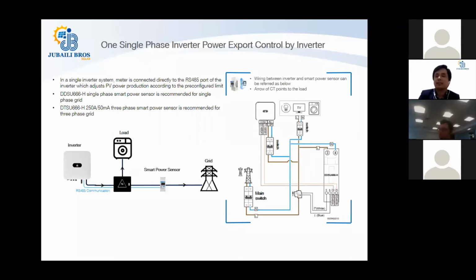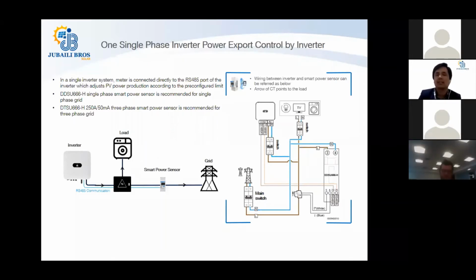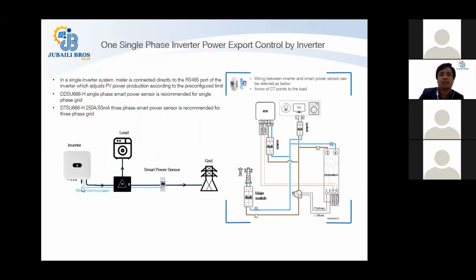This power meter will read the voltage and current, and will understand what exactly power is flowing in which direction. When it goes towards the grid, it will understand that there is excess power which might need control. So depending on your control option, the logic inside the inverter will work and do the necessary control. So in the single phase inverter, you can have a smart power sensor which can be directly connected to the inverter. And you have an option of using the dongle if you need the online monitoring. In some cases, we have seen where people do not require a monitoring option, so you can do this setup without even a dongle as well.